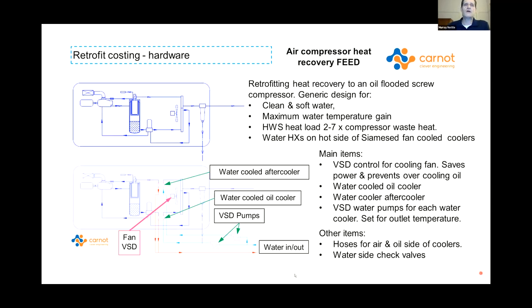So the main thing you're adding is a VSD for the cooling fan. If you don't turn the cooling fan off, it will overcool the oil and still reject heat. So, and it's also direct power saving as well. If you can turn the fan off with a VSD, that's great. The VSD is controlled by the temperature of the oil coming out of the air end. If it gets too hot, the fan starts cooling. Easy.